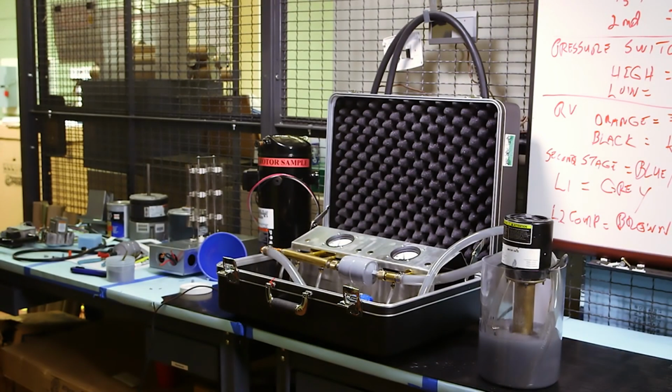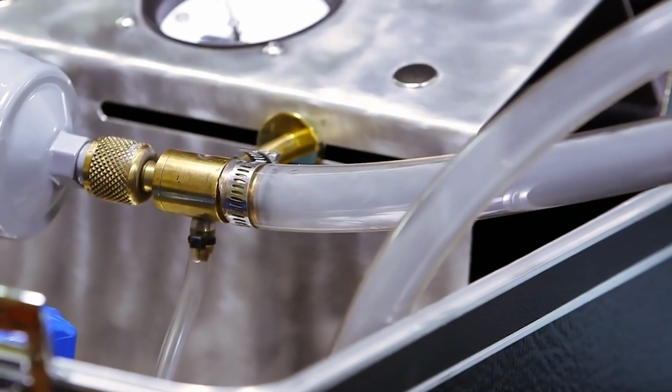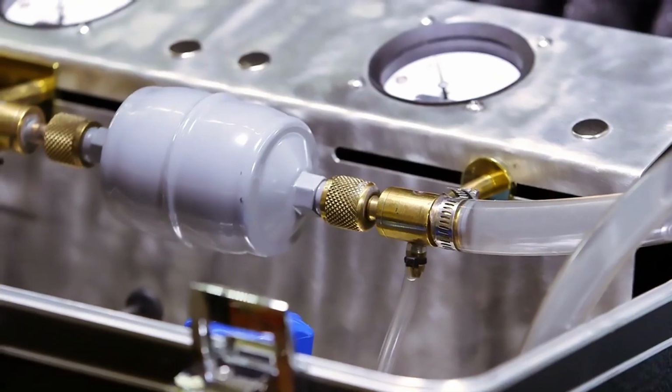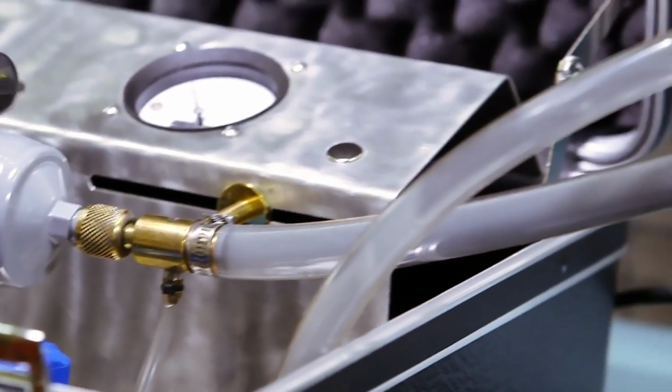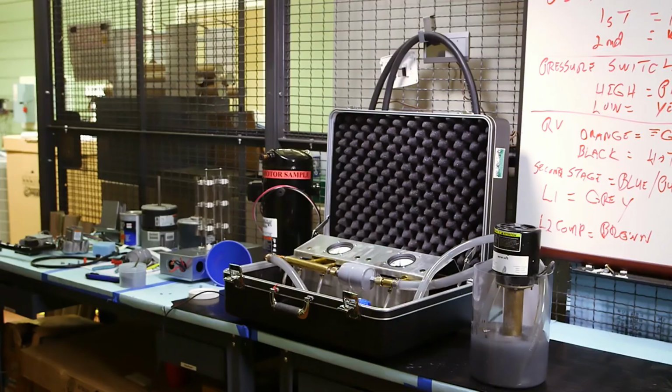We've run the test for almost 3.5 minutes and the refrigerant is still really cloudy. Now, we're going to simulate system cycling. Notice that upon startup, you see the release of contaminant back into the system. You can demonstrate the effect of normal system vibration by tapping on the dryer. There's a substantial release of contaminant back into the system. After more than 4 minutes of operation, the system is still very cloudy.